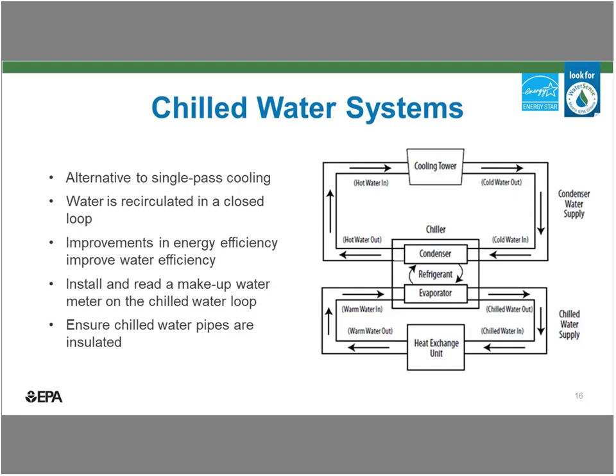So fortunately, most facilities with substantial cooling loads use recirculated chilled water systems. These systems have several key components. There's a heat exchange unit that is supplied with chilled water, providing space cooling or cooling for some other equipment. This is where the heat load really comes from. Number two, there's a chiller unit that generates the chilled water through a refrigeration process.